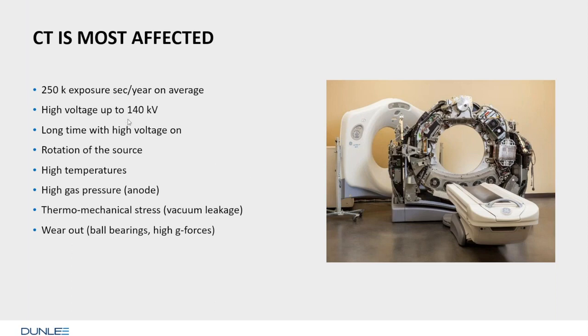The high voltage is also pretty high. Angio works usually at 100 kV max, maybe sometimes 110, but then the contrast is gone. CT works always, or most of the time, with 120 kilovolts, sometimes 140, and one vendor dares to do it at 150. So there's a very high electric field generated by the generators. The rotation of the source is one aspect. If you have microparticles in the tube, they can also cause the discharges.